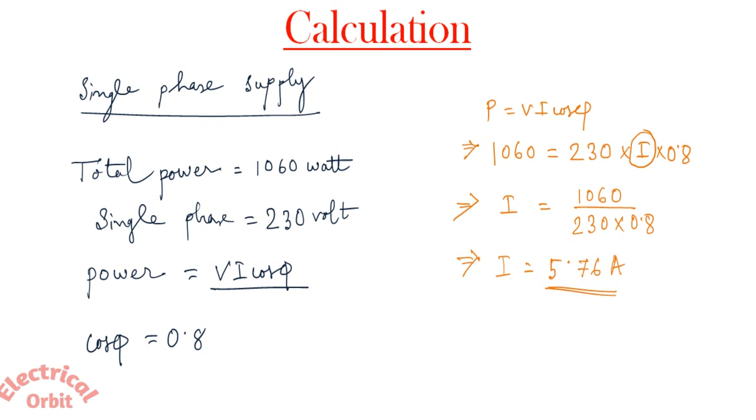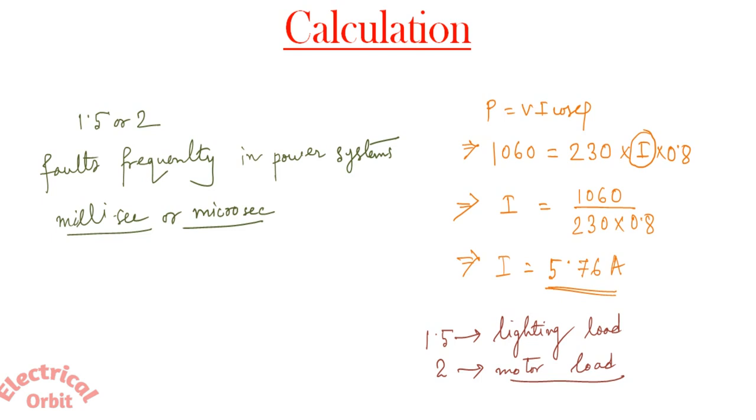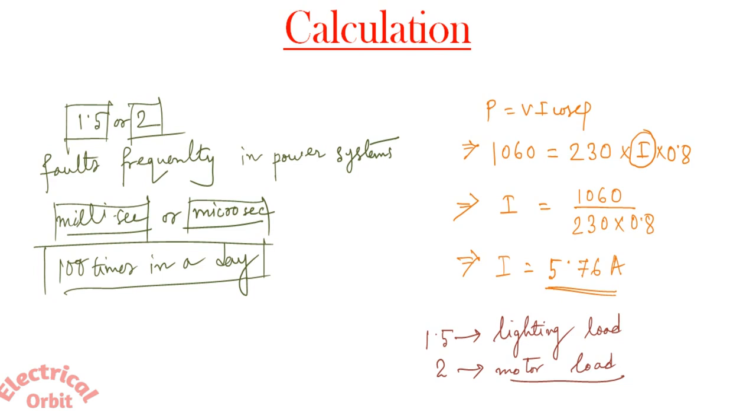Now here two things are very important. First, the value we have achieved by our calculation has to be multiplied with 1.5 for lighting load and with 2 for motor load. The requirement of multiplying this 1.5 or 2 is there are many faults that frequently occur in power system and that sustain for maybe millisecond or microsecond. So if you are not multiplying with these safety factors, then your breaker or MCB will go on tripping hundreds of times in a day. And for the sake of this millisecond or microsecond fault, your system is not going to be burnt out or there is any kind of losses that you will encounter. So this is very important factor for that it is multiplied.